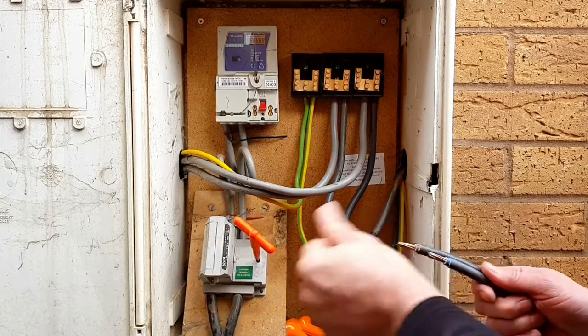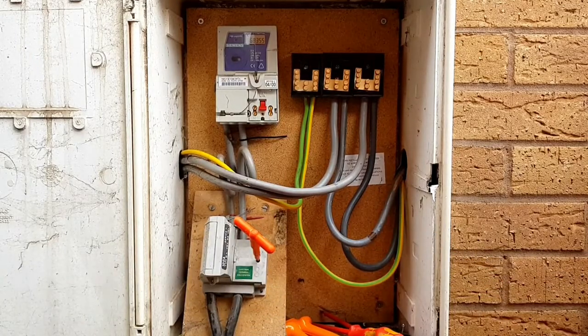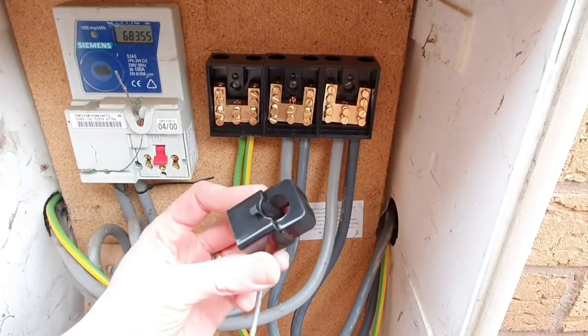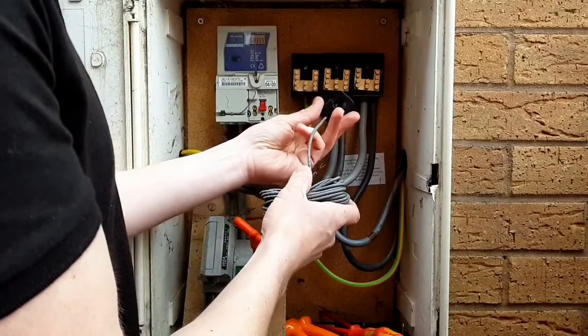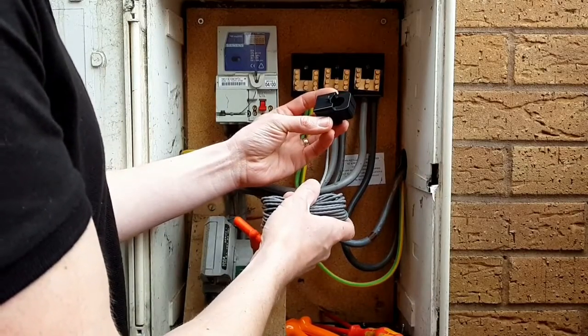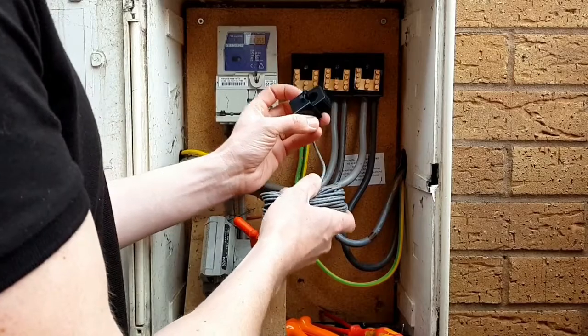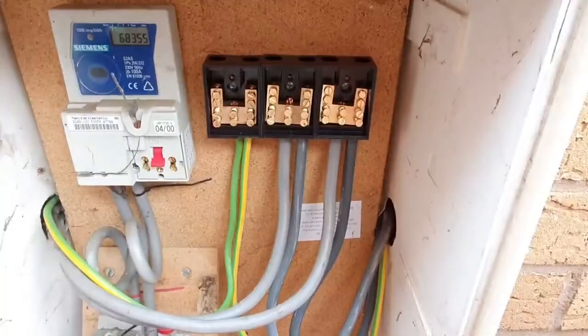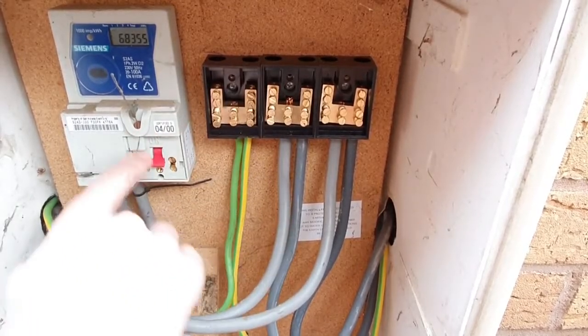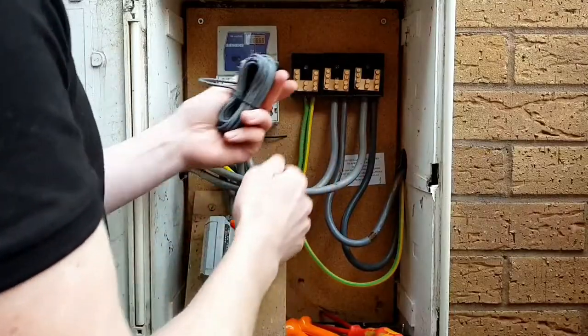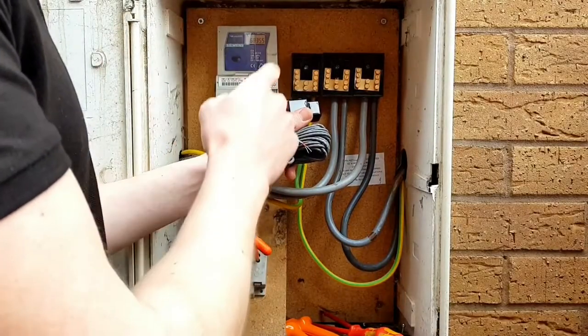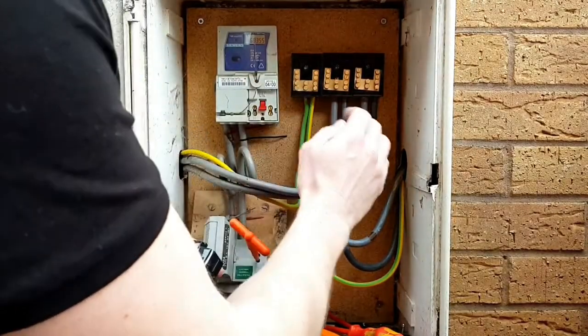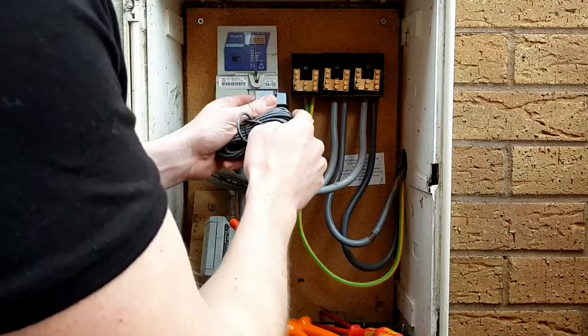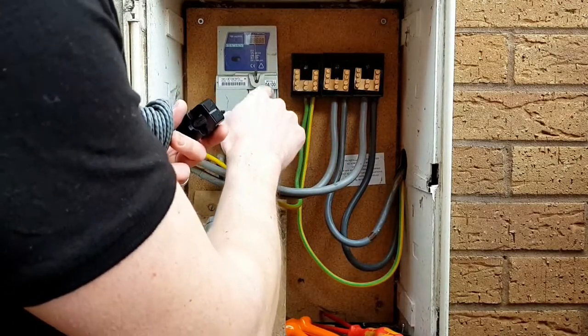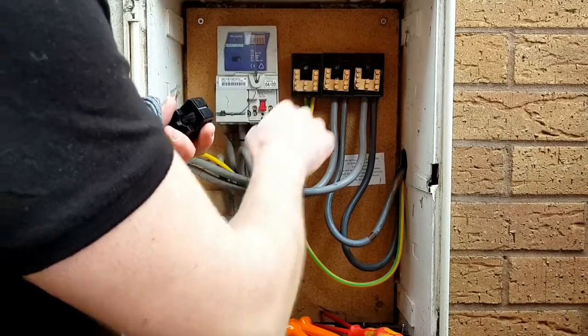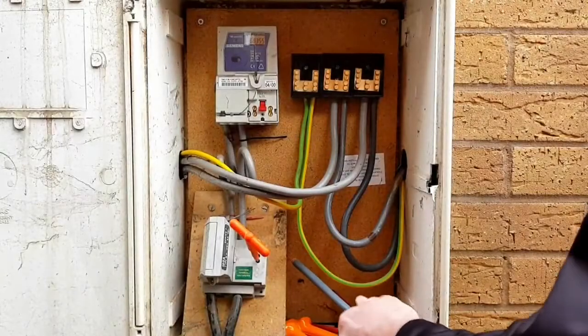Absolutely. So I think we grab the CT, have a little look at that, see where it's going to go, and then we'll talk about getting these tails installed. So here we've got our current transformer. This is our CT that we're going to be using to monitor the current that's flowing into the installation, and we need to have this wrapped around essentially the main conductor, the line conductor that feeds the property. So this is going to be able to monitor all of the current that's flowing into the building, not just the current flowing into the existing installation, not just the current flowing into our new installation, but the whole current. So it must go on the conductor that goes from the live terminal in the meter to your first Henley block. So let's get these tails installed then, Gary.